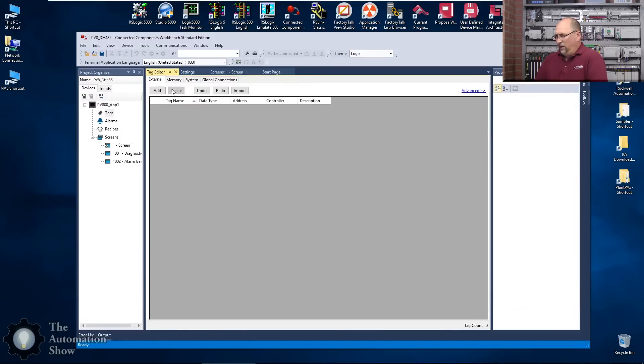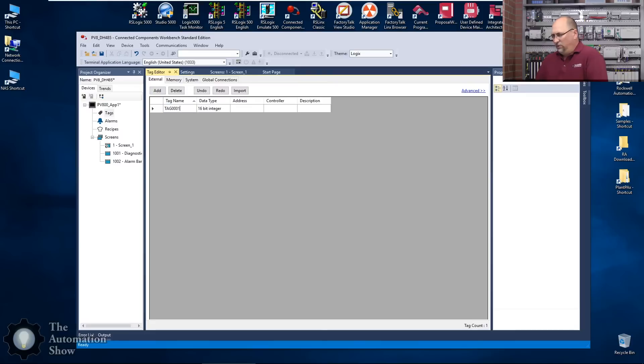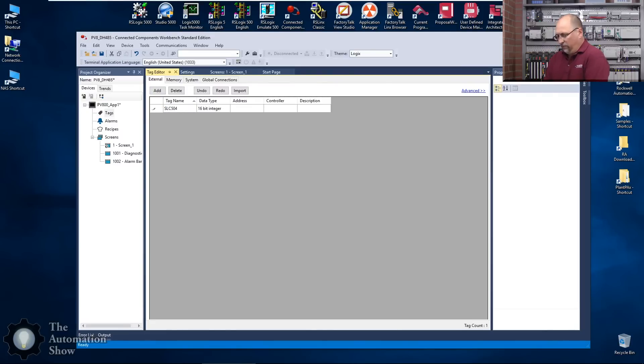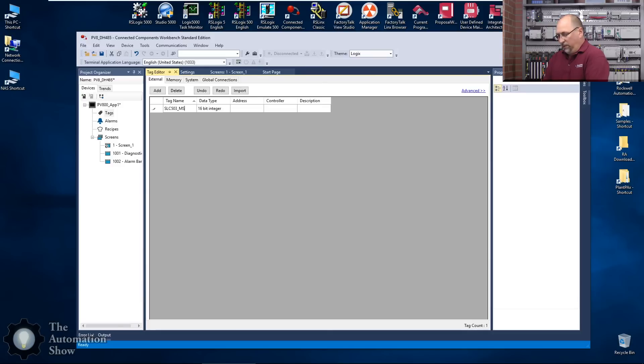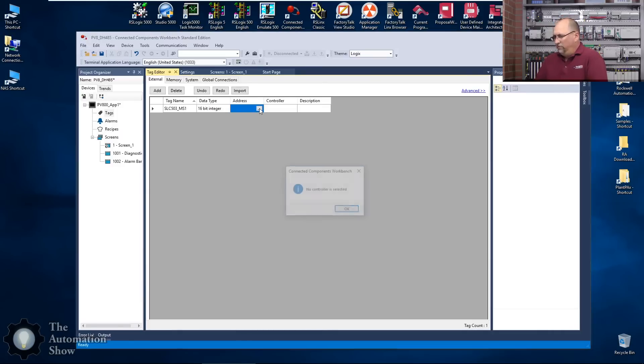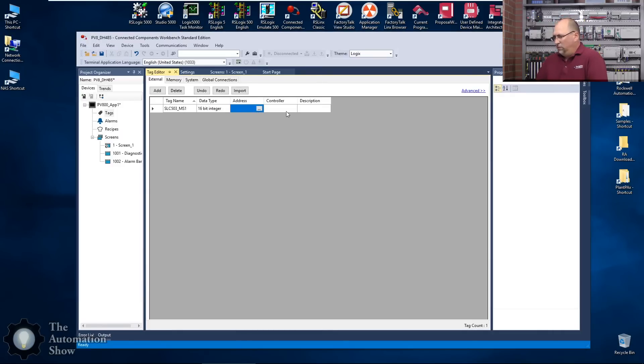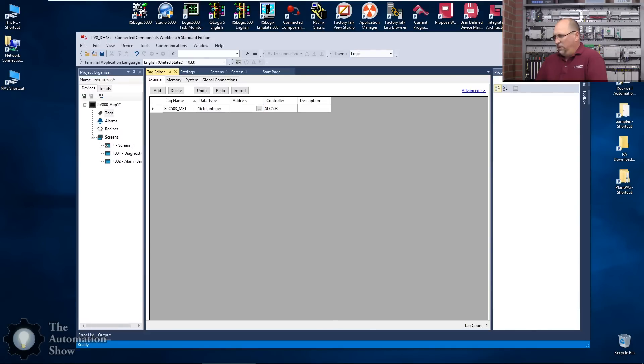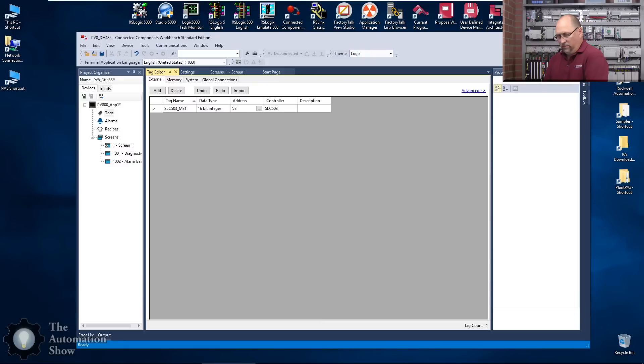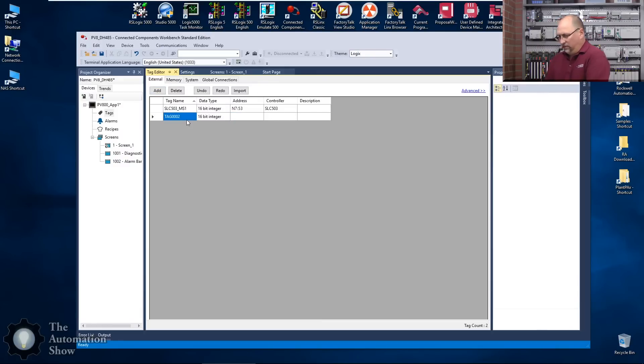We'll go to Tags. We'll add some tags and for the sake of brevity I'll just do one from each. So we'll do SLC_503_mold_speed_1. And that address will be, whoops, let me select the controller here first, and then that address will be N7:53. Now we'll add another tag, we'll call this MicroLogix_1200_mold_speed_1.